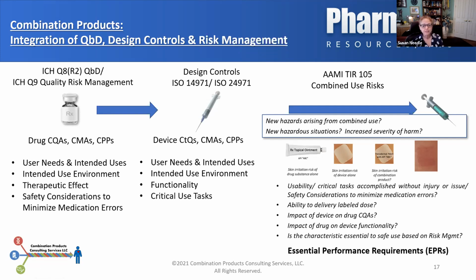As we look at those combined use risks, the FDA issued ICH-Q12, which is post-market considerations. There is a draft guidance that was issued on implementation of ICH-Q12, and there's a wonderful decision tree in that draft guidance. I've added a question to it, which I'm going to mention in a moment. The questions called out in that decision tree are really good when you're thinking about the combined use risks, or the essential performance requirements associated with the device constituent of my combination product. Those requirements tend to be: are there usability or critical tasks being accomplished, and are they accomplished without injury or issue, so that I am taking into account the safety considerations to minimize medication errors.